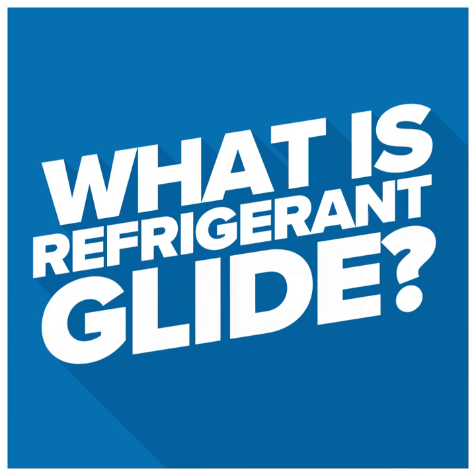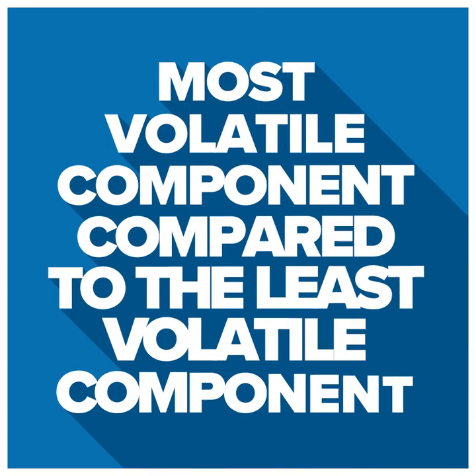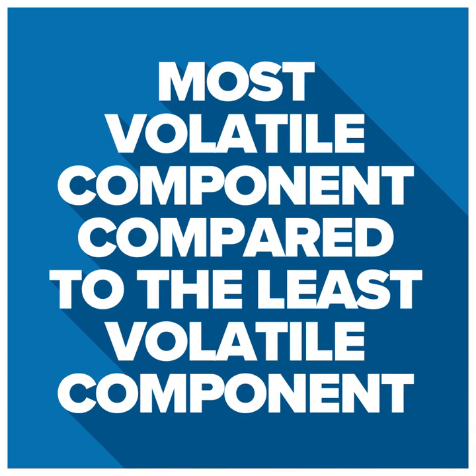But you may ask, what is a refrigerant glide? Glide is the difference between the boiling point of the most volatile component compared to the least volatile component within the refrigerant blend.